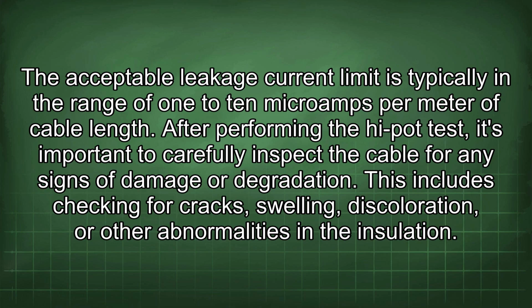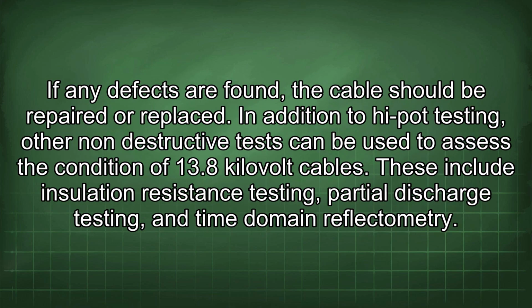After performing the high-pot test, it's important to carefully inspect the cable for any signs of damage or degradation. This includes checking for cracks, swelling, discoloration, or other abnormalities in the insulation. If any defects are found, the cable should be repaired or replaced. In addition to high-pot testing, other non-destructive tests can be used to assess the condition of 13.8 kV cables. These include insulation resistance testing, partial discharge testing, and time domain reflectometry.